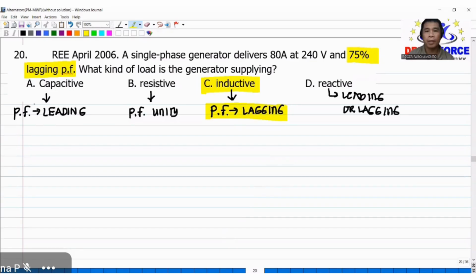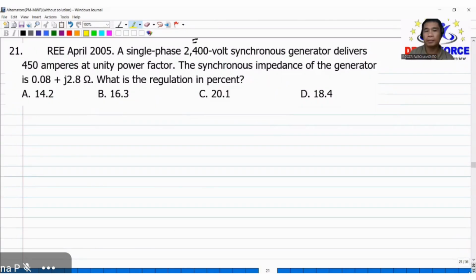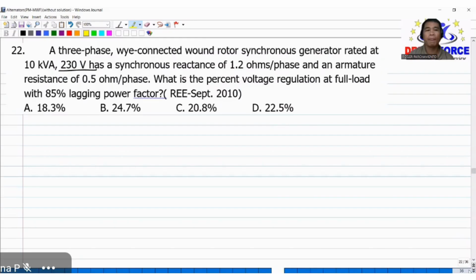Anyway, it is not advisable to have a leading power factor because later on you will see the effect. If you have a leading power factor, you will have a higher output voltage at a lower generated voltage. So in that case, you will have the effect of overload, over voltage.